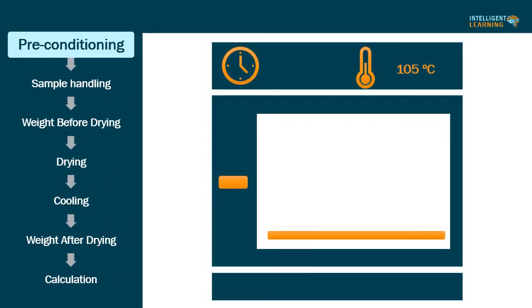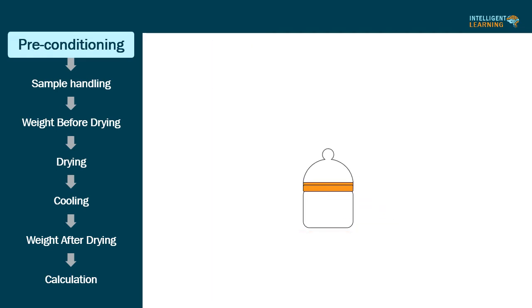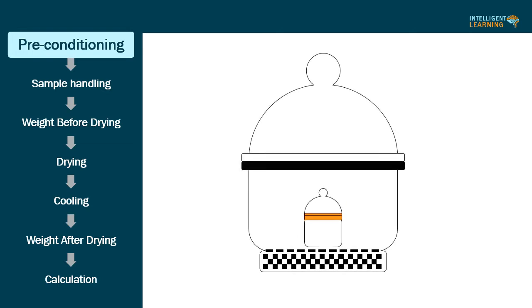First step: preconditioning. Set the temperature of the drying chamber as per the method of analysis. Maintain the temperature of the drying oven at plus or minus 2 degrees Celsius. After reaching the desired temperature, dry the glass stoppered weighing bottle for about 30 minutes at the same temperature. Remove the glass stoppered weighing bottle from the drying chamber and cool to room temperature in a desiccator.